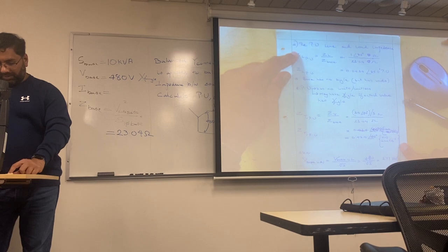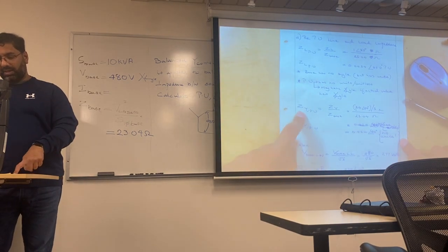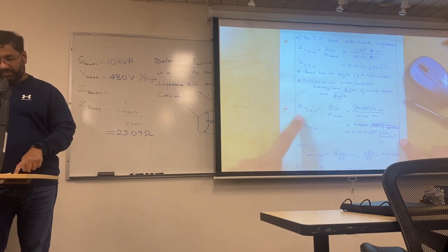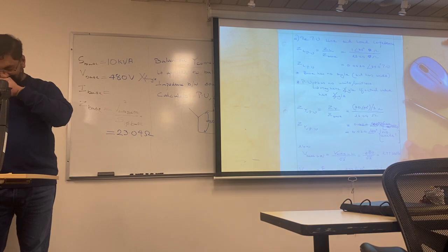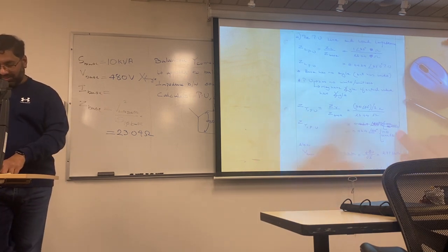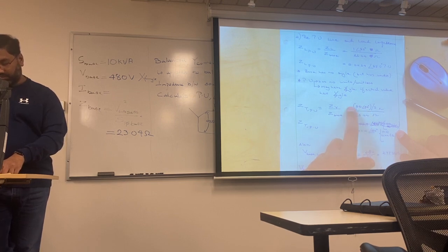So we just figured out our first per unit for the Z of the line. Now we are going for the Y, load system, or the ZY. So you have your load with an impedance of 30 with an angle of 40. And that was a delta system. To get into Y, I divided by 3, and that pops from this guy.